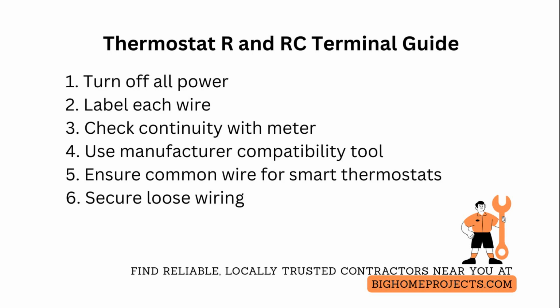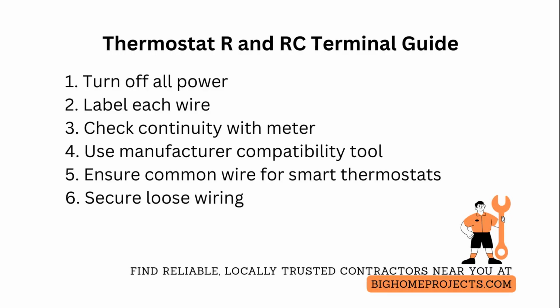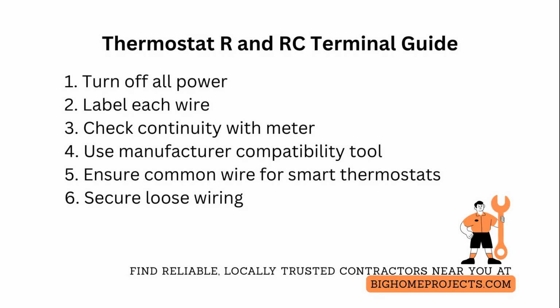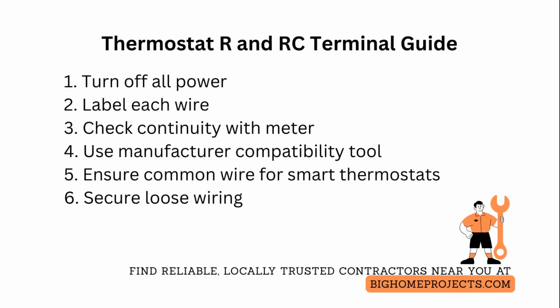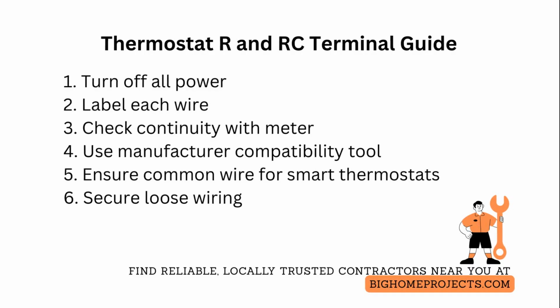When replacing a thermostat, first turn off all power at the furnace and outdoor unit, then label each wire with its letter using masking tape before disconnecting so you retain exact function mapping. Check continuity with a meter if you suspect a shared common or a broken wire. Use the thermostat manufacturer's compatibility tool or the wiring diagram from the control board to confirm which terminal corresponds to heating call, cooling call, fan, and common.